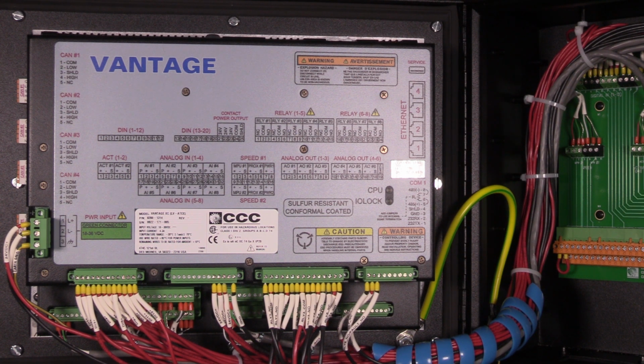For robust communications performance, the CAN cabling needs to minimize the exposed non-shielded cable section that occurs at terminal block section. The exposed length of CAN wiring must be limited to less than 3.8 centimeters or 1.5 inches from the end of the shield to the terminal block. If multiple connections need to be made, CCC recommends daisy chain connections.